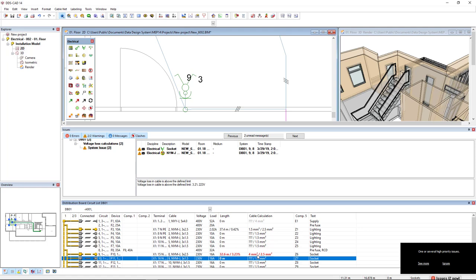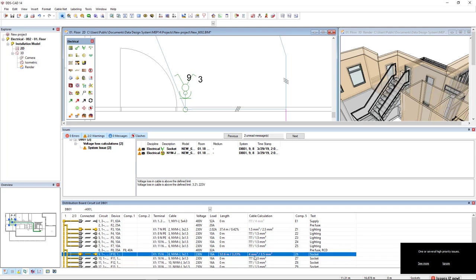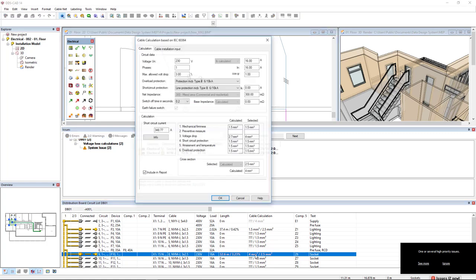What we can see here is that on the left we have the length, the calculated length, and we have the voltage drop that we see also in the indication in the issues list. On the right, we see that DDSCAD calculated 4 square millimeters. If we double click here, this entry in the cable calculation column, we see here the results.